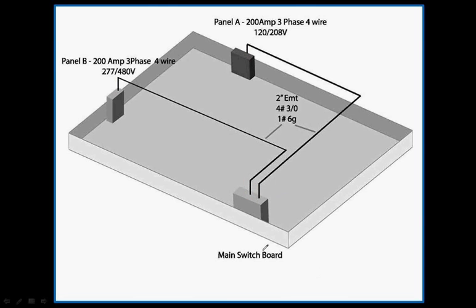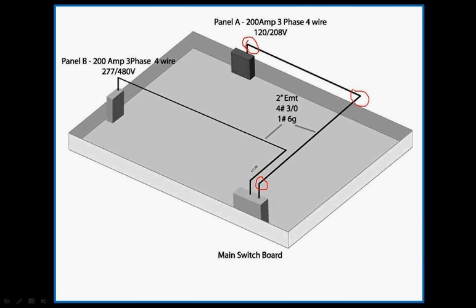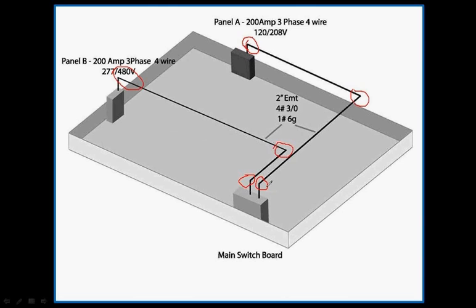Next, let's look at our second point. Our second point is conduit elbows or 90-degree bends. The number of elbows will be input into Rhino so you can capture their material cost and the labor required to install them. I'm circling them here so you can understand what the 90s are. Now, this is a three-dimensional drawing, but on the usual drawing that you'll be doing a takeoff from, you won't see where the 90s are required to be, so you'll have to figure that yourself. You'll have to figure out how many 90s you need in each conduit run.